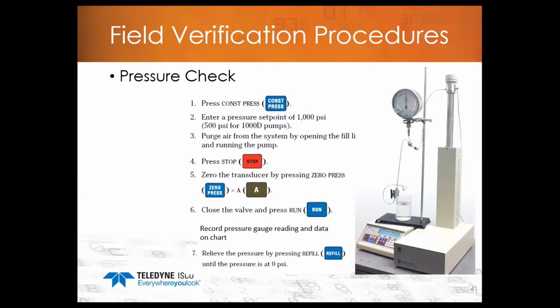So R53 sets your span. Once you've got it under pressure and it's stabilized, then you'll adjust R53 so that your pressure gauge matches the reading on the controller. So in this case, you would adjust R53 so that your pressure gauge reads 1,000 psi, which will match the pressure reading on the controller.